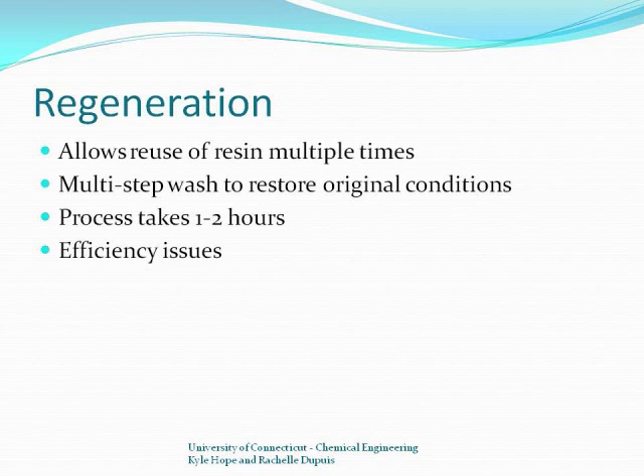Regeneration begins by backwashing the system to dislodge any trapped particles and to fluidize the resin. This is followed by a slow wash with the regenerant solution, which is a dissociative solution that provides the ions necessary for exchange, such as hydrochloric acid or sodium hydroxide. Next, another slow rinse occurs with water to remove any residual regenerant solution. Finally, a fast rinse takes place as an extra precaution against residual regenerant solution. At this point, regeneration is complete and the resin can be used for another cycle.